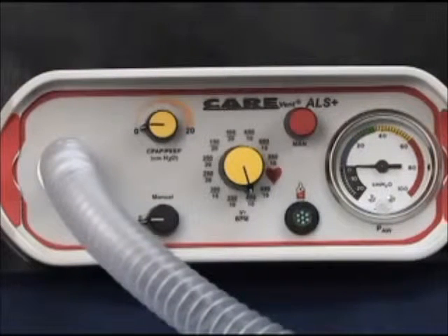In the automatic mode, should the patient commence breathing spontaneously, the CAREvent ALS Plus or ALS Plus CPAP ventilators will sense the patient's inspiratory effort, and the auto shutoff circuit will stop the automatic cycling of the ventilator if the patient's spontaneous flow rate exceeds 30 liters per minute for greater than 1 second. This allows the patient to demand breathe at up to 120 liters per minute on 100% oxygen at their own rate and volume.